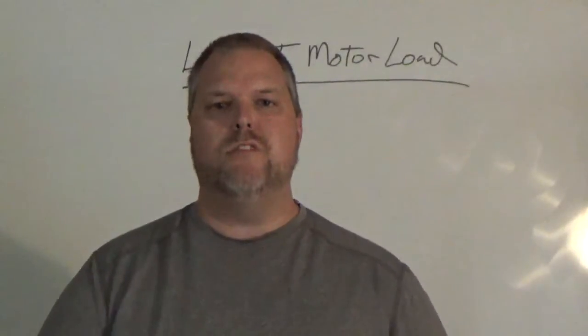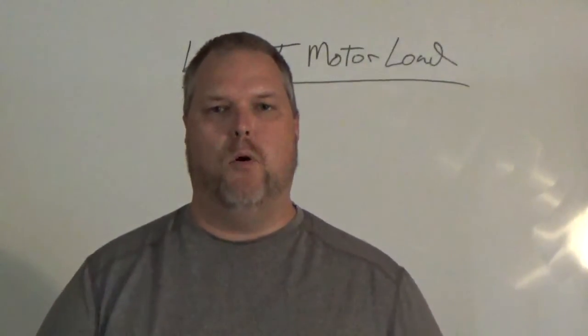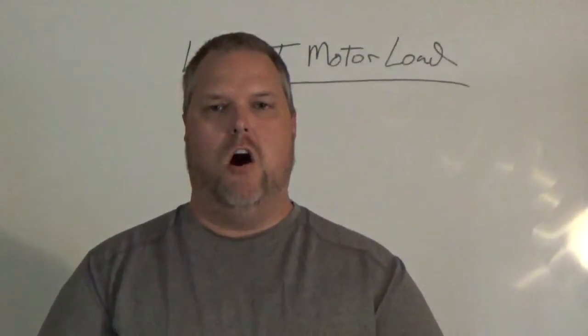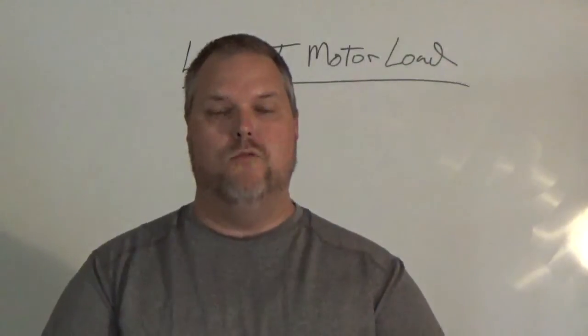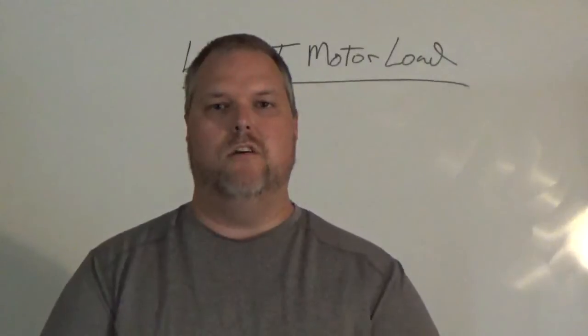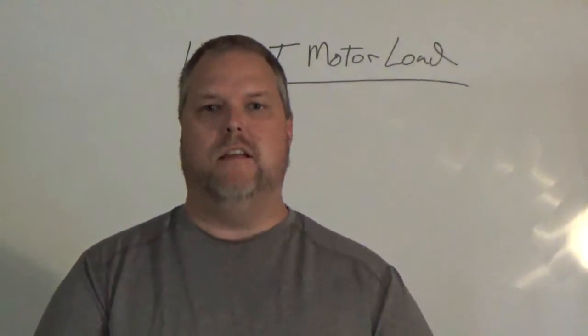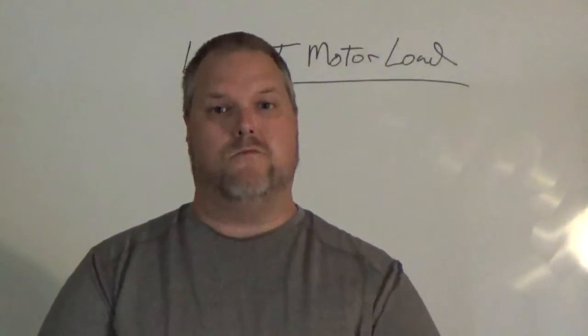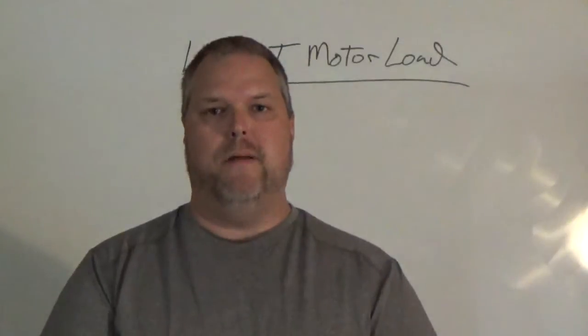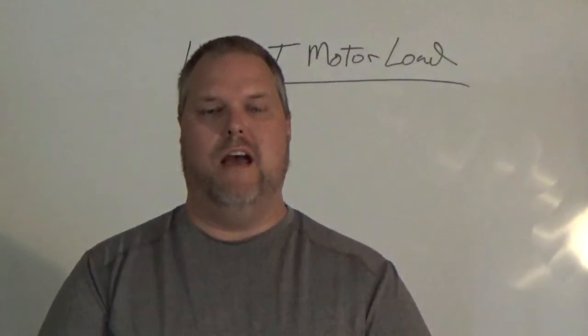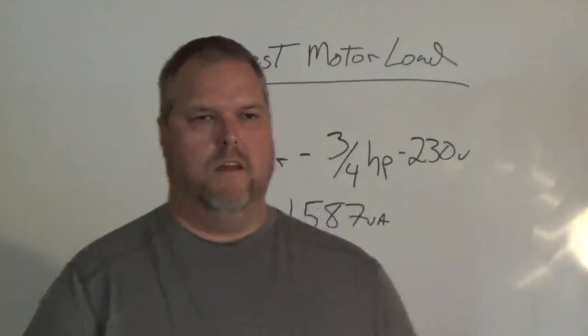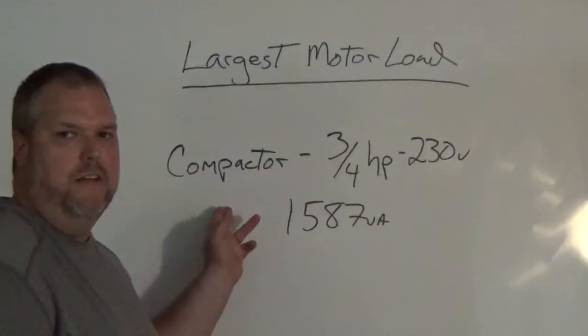Remember, the key is: if AC is not taken, if it's been omitted from the calculation, you cannot use it as the largest motor. It's very important you understand this. This is one of the hardest things students have understanding—that you can't use the AC even though it is the largest motor. So we're going to refer back to the same calculation we did in fixed appliances in our other video. Now we have to determine which is our largest motor.